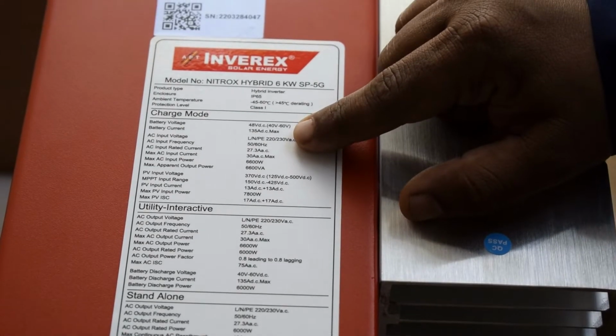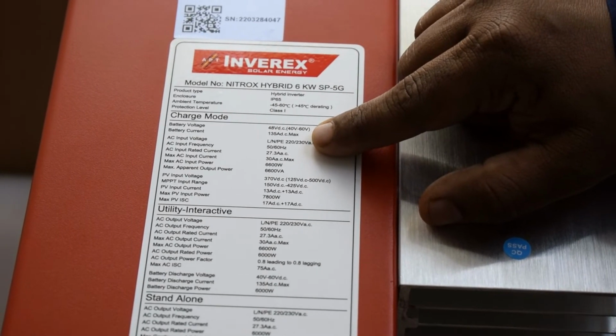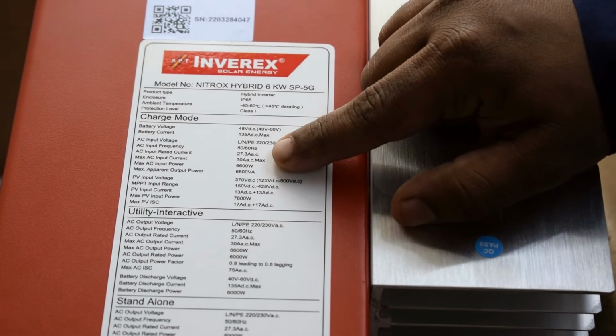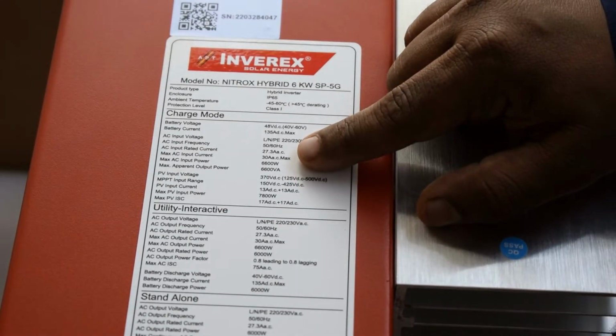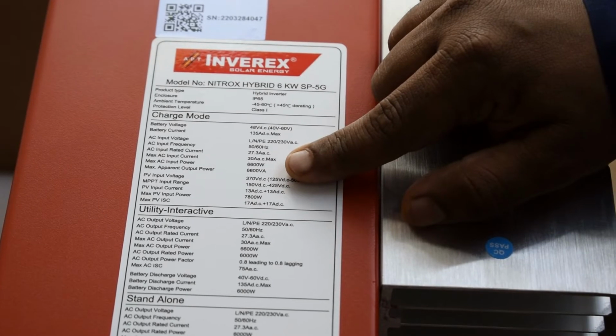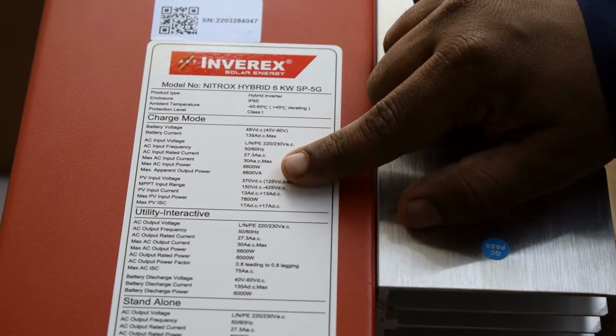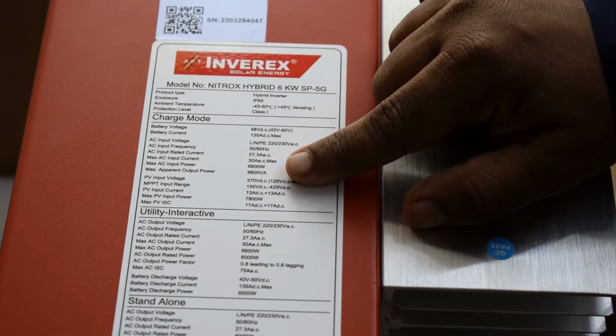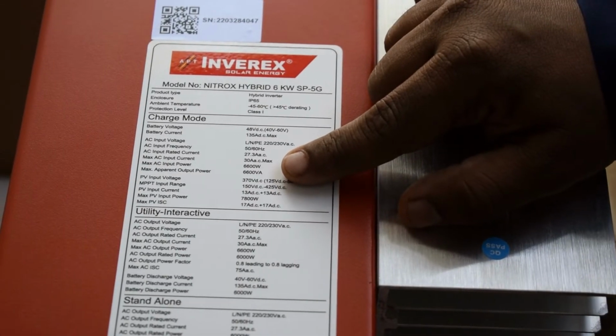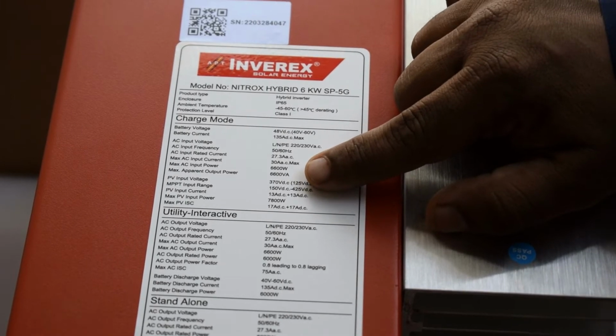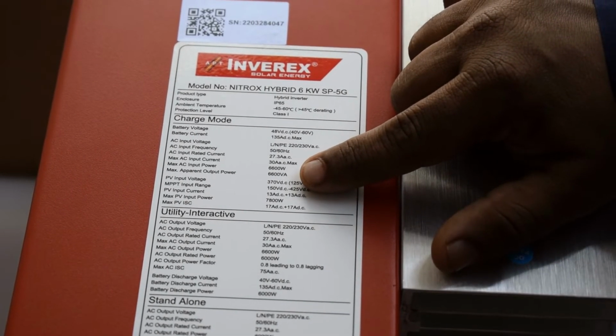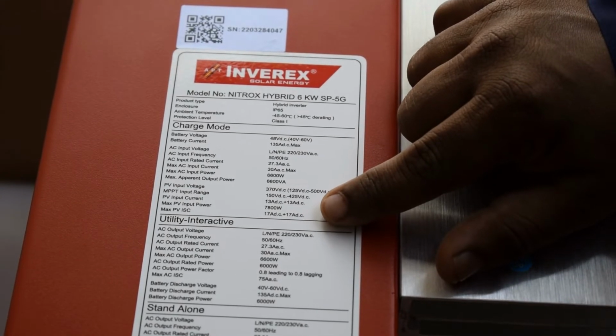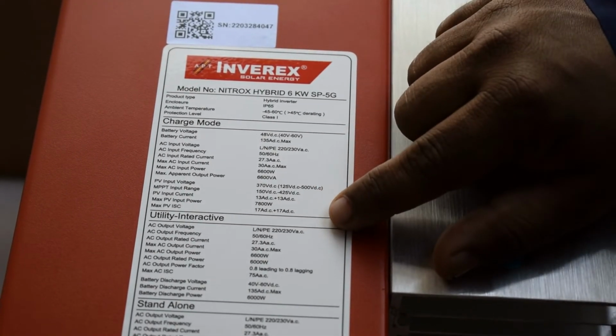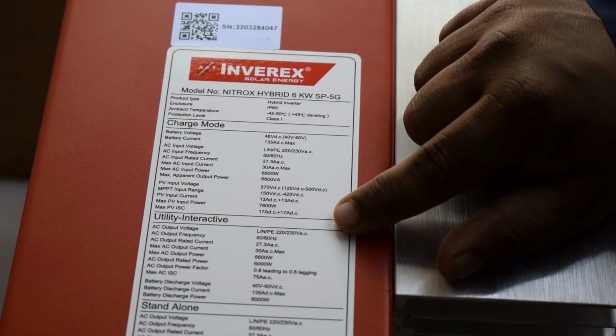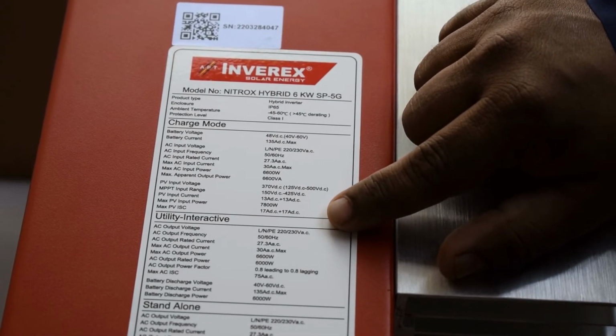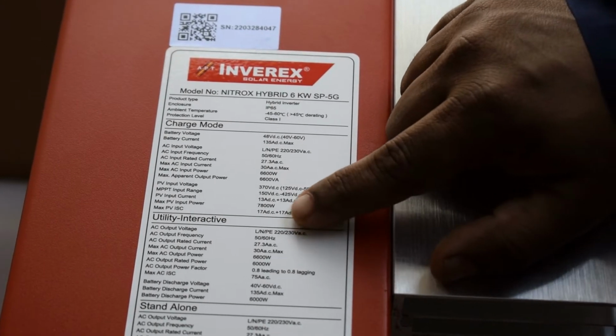The maximum battery current is 135 ampere DC. For the AC power, the frequency is selectable from 50 to 60. We have AC current of 27 ampere maximum, and the maximum AC power connected to this inverter would be 6000 watt. So it's 6 kilowatt, or 6.6 kVA. We have a power factor of 0.8 leading to lagging, and the maximum PV input voltage is 370 volt, 150 volt for MPPTs, and 13 ampere for the solar string.